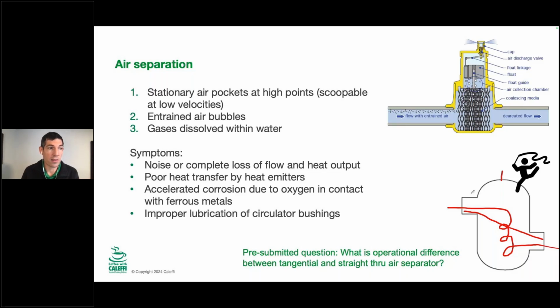So again, they will work. It's just not something that works across the entire range of flow rates, the same way that an air separator has a good range from 1 GPM to whatever its maximum GPM is. So without that vortex, you're kind of missing something. If you've got a single speed pump and it's always going to be exactly that condition, then a tangential separator sized correctly will work. But if you've got an ECM pump, if you've got variable flow, you might have that just crossing straight across an expensive commercial device, and that's not what we're looking for there.